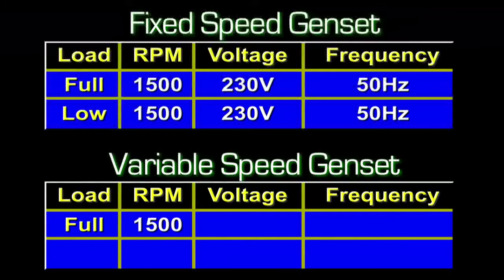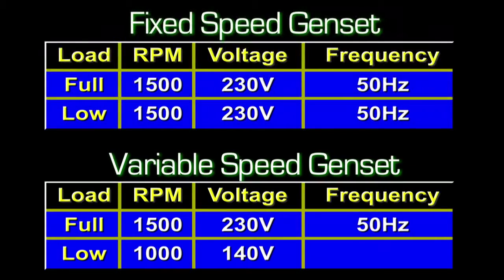The variable speed genset runs at 1500 RPM and develops 230 volts AC at 50 Hz only in full load condition. In low load condition, the variable speed genset smartly reduces its speed to as low as 1000 RPM. The genset output can be as low as 140 volt at 33 Hz.